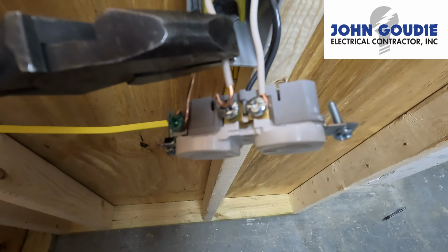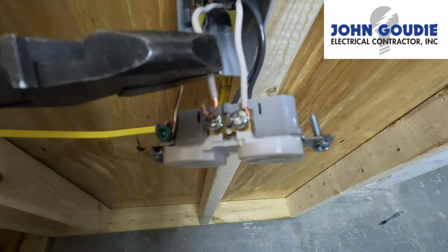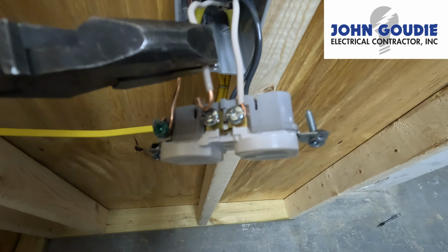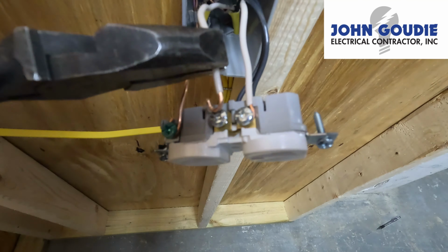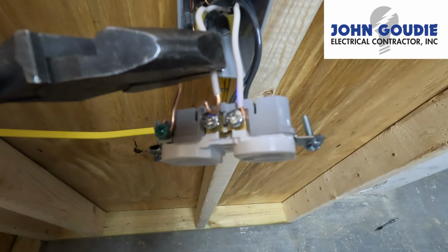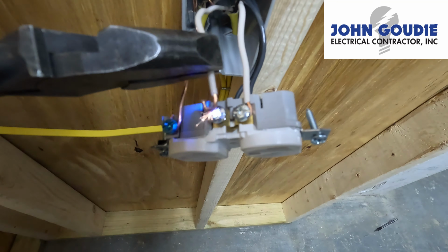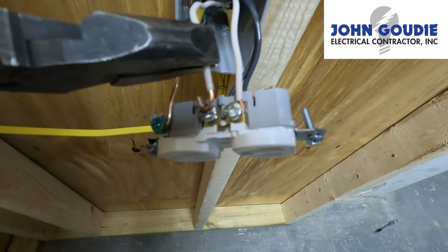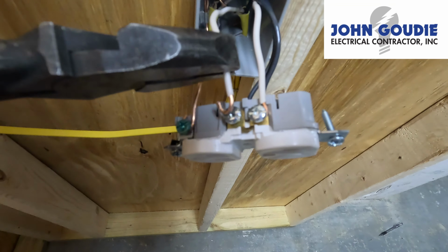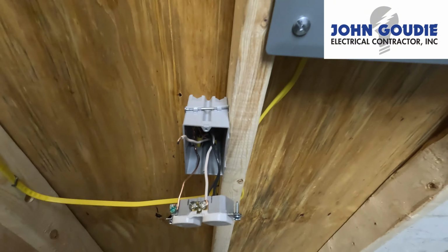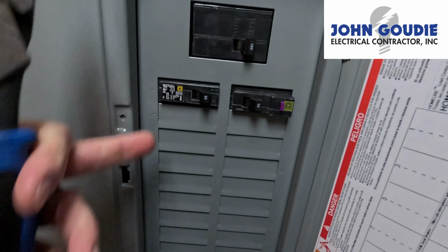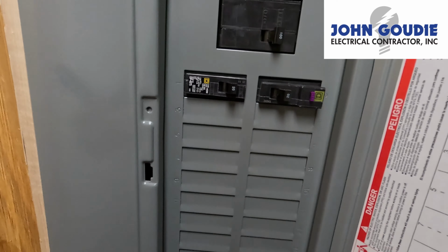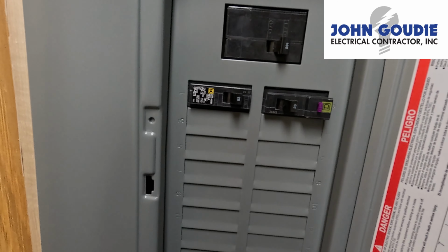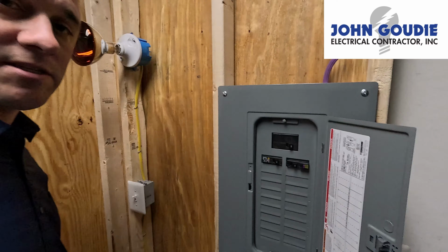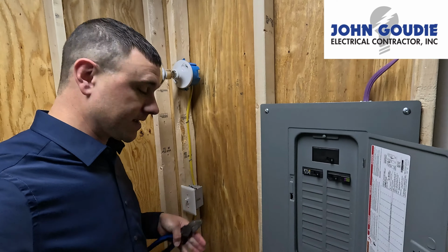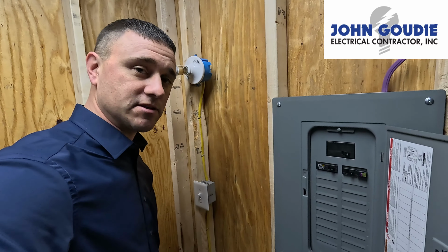I've got over 20 years of experience with electricity, so this is no big deal to me, but don't try this at home. So this is what happens with a loose electrical connection. Any kind of appliance that you have plugged in, or maybe you have a loose connection within your duplex receptacles, your switches, or light fixtures inside of your home, this is what happens when the connection gets loose, and this is how fires start. Right now, this circuit is connected to this normal 20 amp miniature circuit breaker. Now I'm going to switch that around, and connect this circuit to the arc fault and let you see what happens.